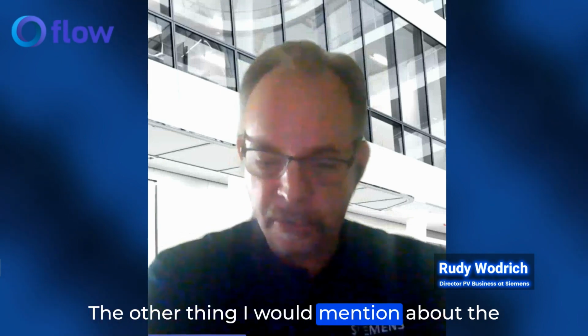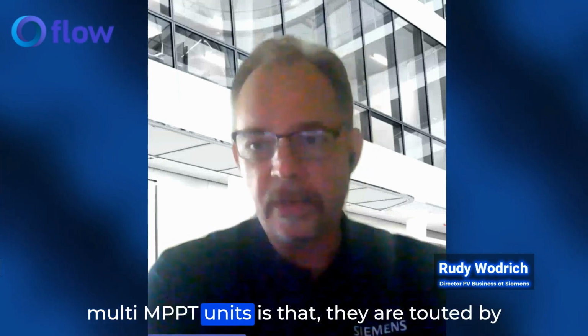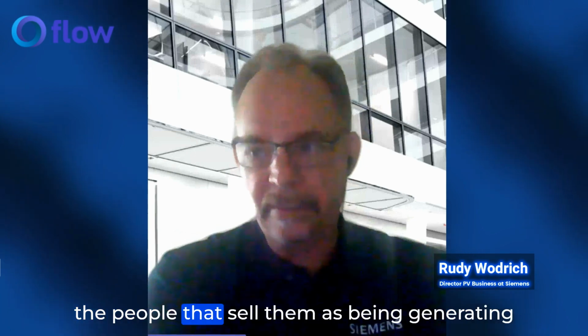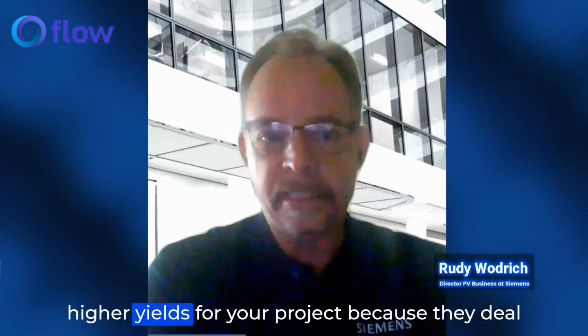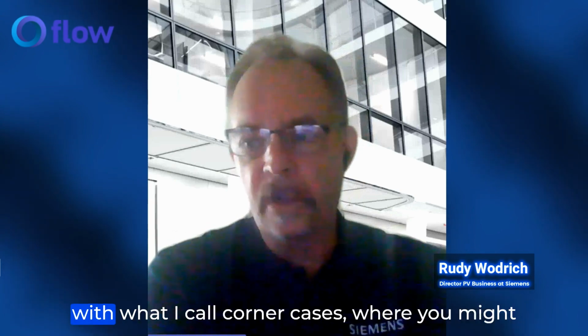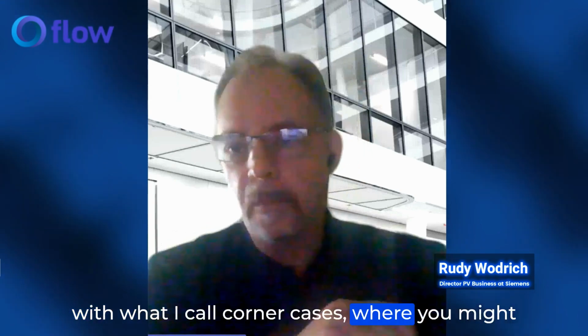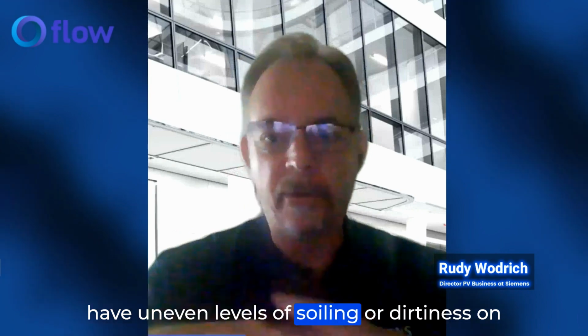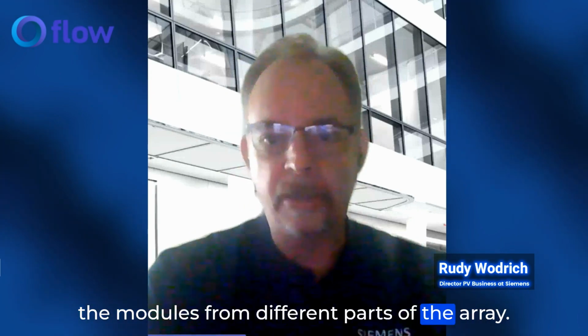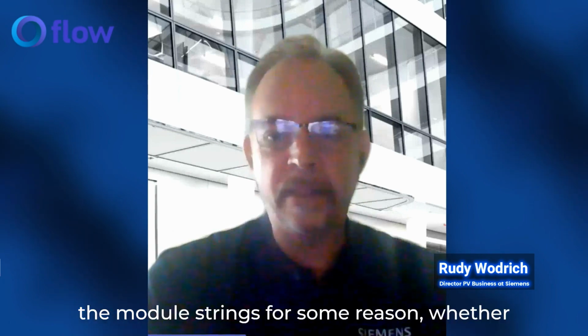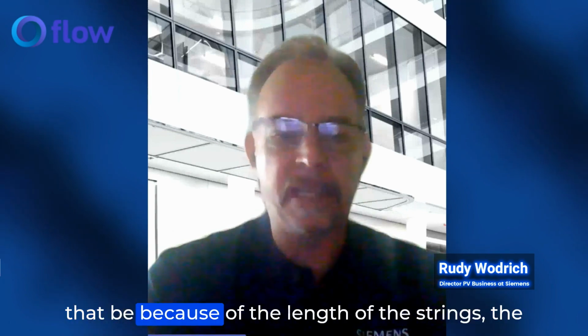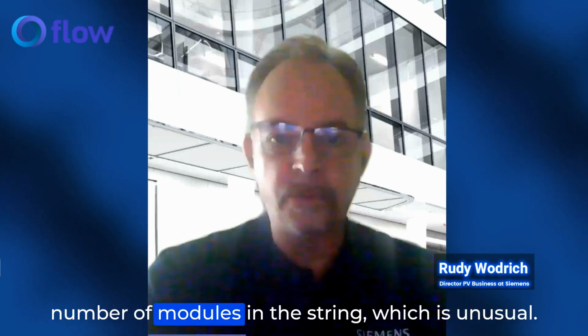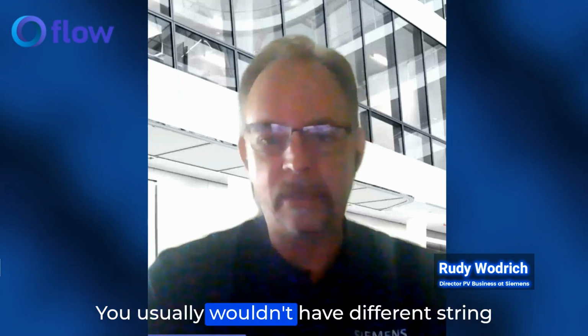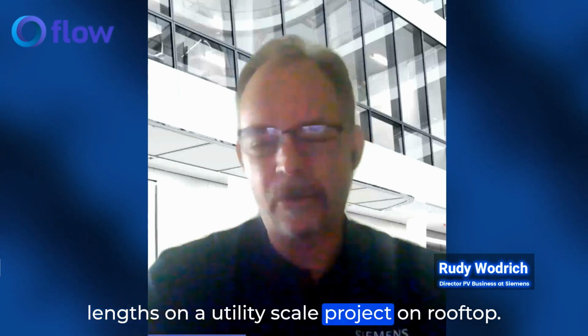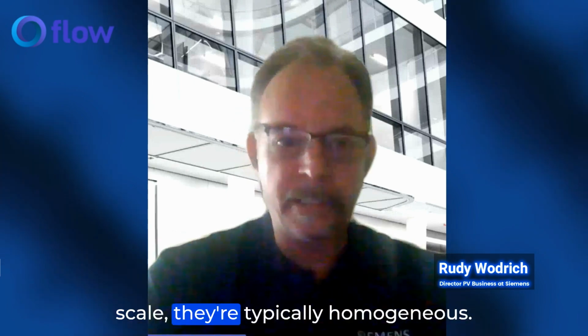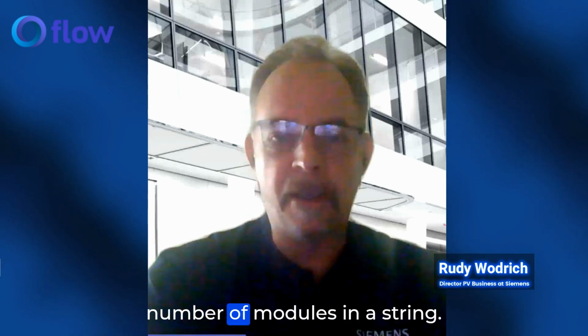The other thing about multi-MPPT units is that they're touted by the people that sell them as generating higher yields because they deal with corner cases, like uneven soiling or dirtiness on modules in different parts of the array, or mismatches between module strings due to string length or number of modules, which is unusual. You usually wouldn't have different string lengths on a utility scale project. On rooftops, sometimes you do, but utility scale projects are typically homogeneous, always the same number of modules in a string.